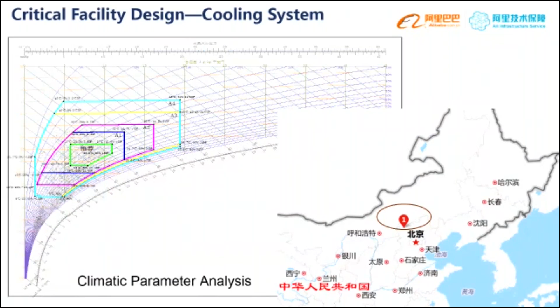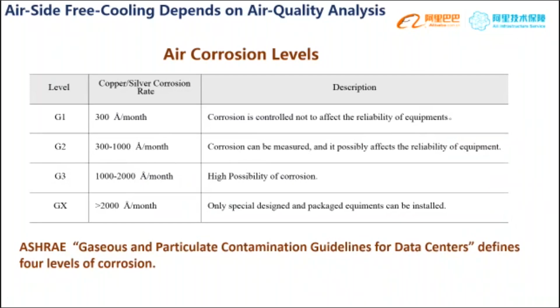Air in Zhangbei is very clean, so direct air side economizer can be taken into consideration. Four levels of air corrosion are defined in the ASHRAE gaseous and particulate contamination guidelines for data centers, ranging from G1 to GX. We all know G1 and G2 level air can enter the data center directly.